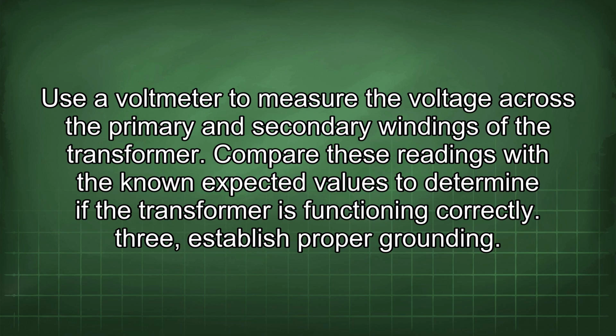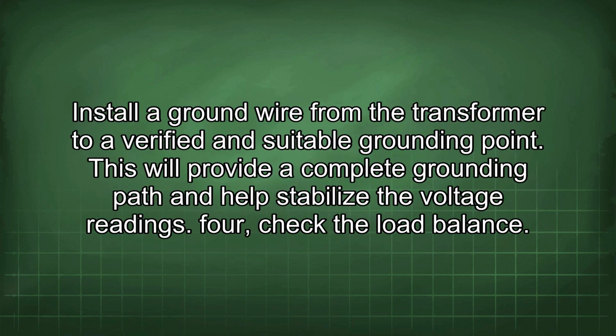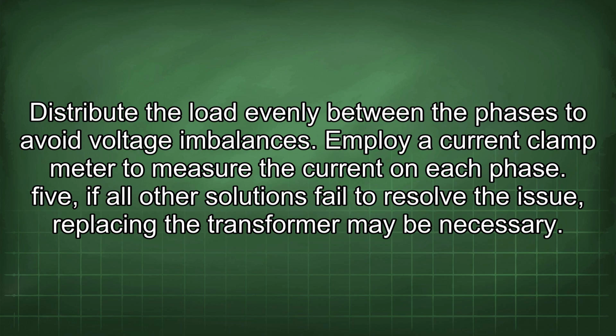3. Establish proper grounding. Install a ground wire from the transformer to a verified and suitable grounding point. This will provide a complete grounding path and help stabilize the voltage readings. 4. Check the load balance. Distribute the load evenly between the phases to avoid voltage imbalances. Employ a current clamp meter to measure the current on each phase.